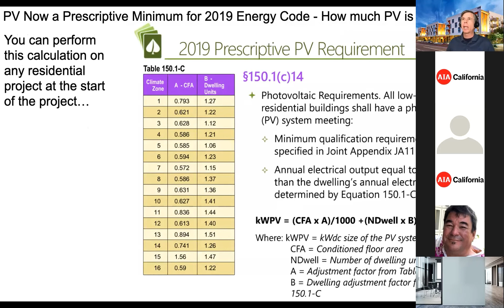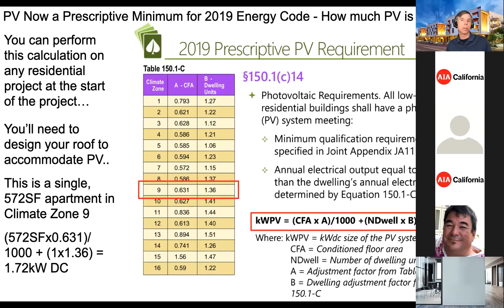For any residential project, at the start you have to understand how you're going to land the required amount of PV on your roof. Here's the calculation for a 572 square foot apartment in climate zone 9. The size of the PV system equals the conditioned floor area times column A divided by 1,000, plus the number of dwelling units times column B. If I do that for this building, I end up with a 1.72 kW PV system. It's a one bedroom apartment, so not a huge system here.